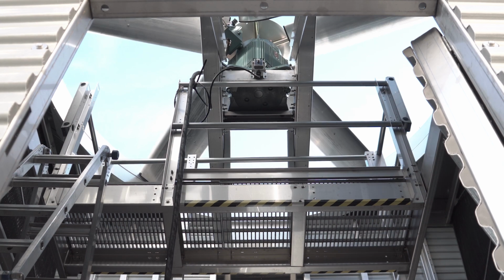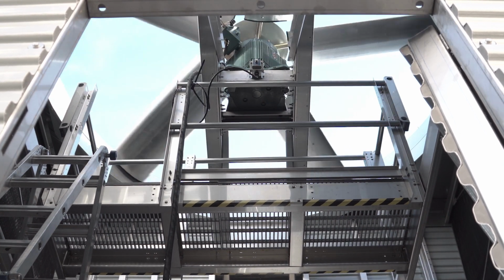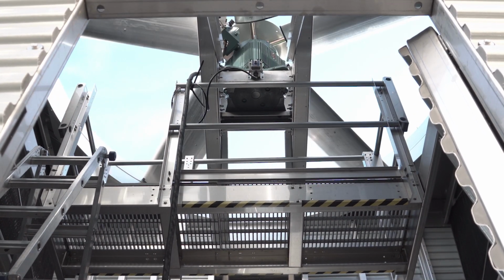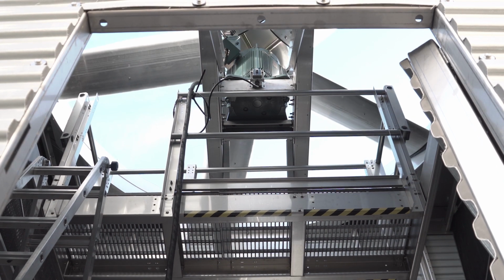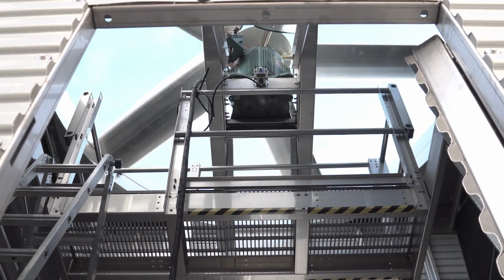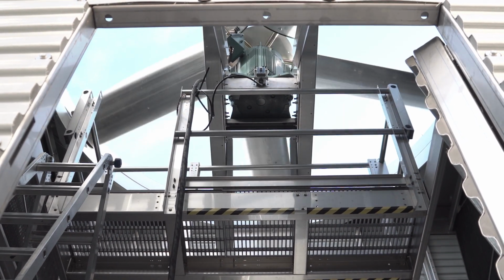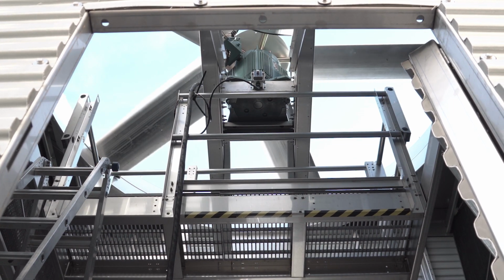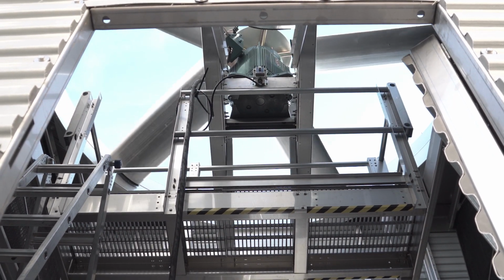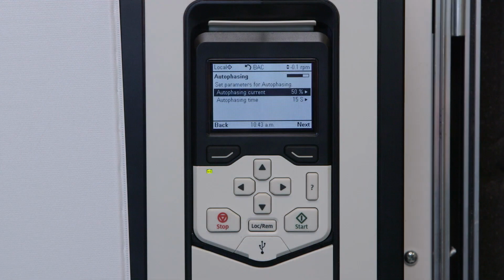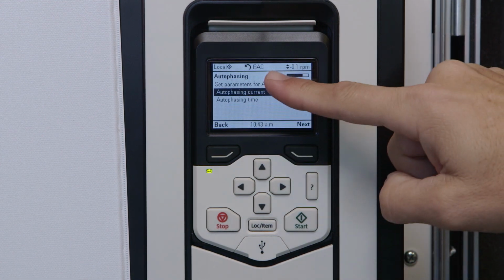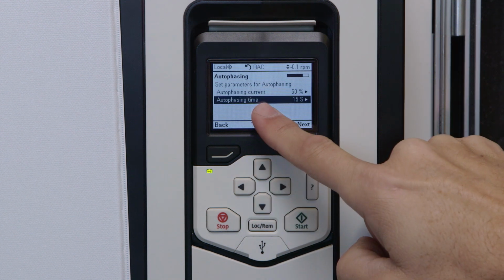If the motor is not turning at all, or if the motor cogs back and forth, you will need to adjust the auto phasing on the direction test screen. This is the automatic routine that lines up the motor magnets to the electric motor poles. The routine is automatically performed on every start signal. If you need to adjust the auto phasing, scroll to Auto Phasing menu and increase the auto phase time to 20 seconds.